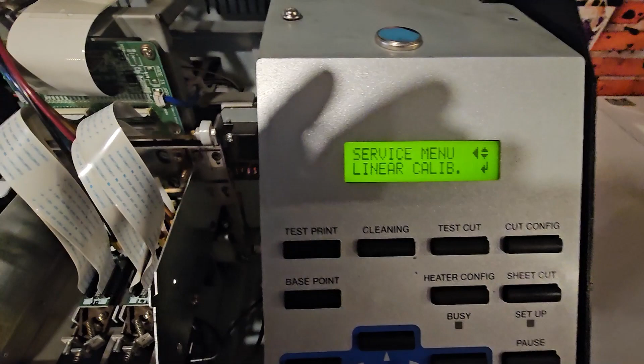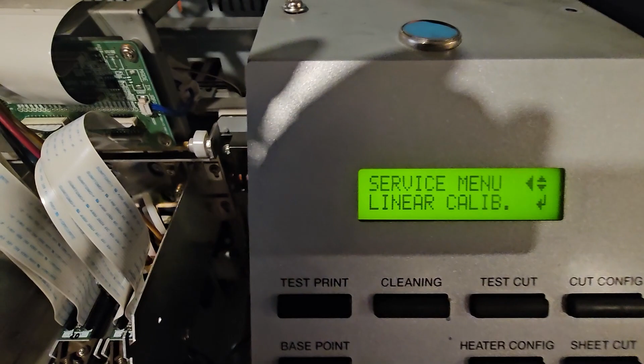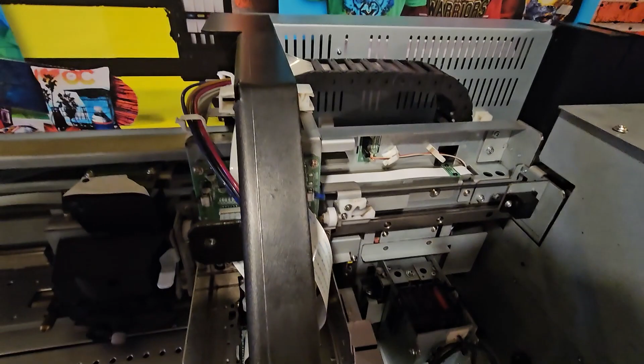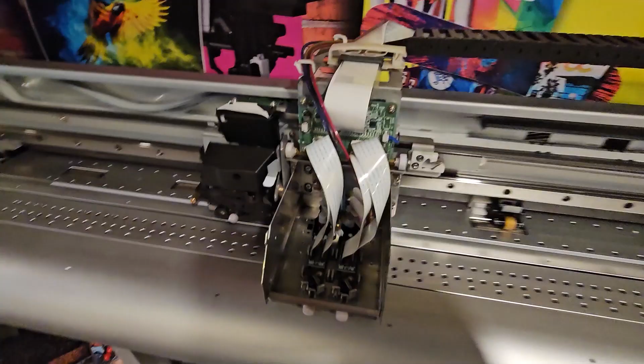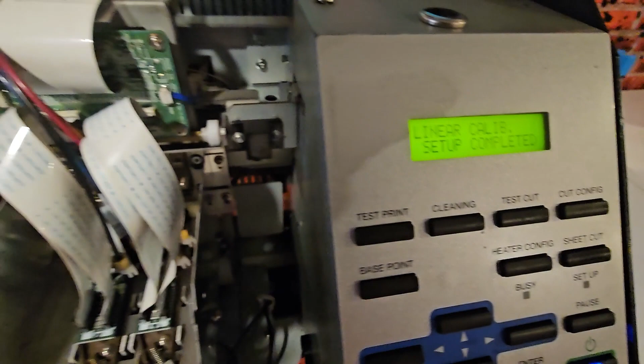The next thing I'm gonna go back to do is my linear calibration. You wanna do this anytime you replace the encoder. Definitely run this test. Here we go. Now it's calibrating itself. It doesn't hurt to do this when you're doing normal maintenance as well. Make sure you're in full calibration. There we go. Again, it's set up completely like it was supposed to.